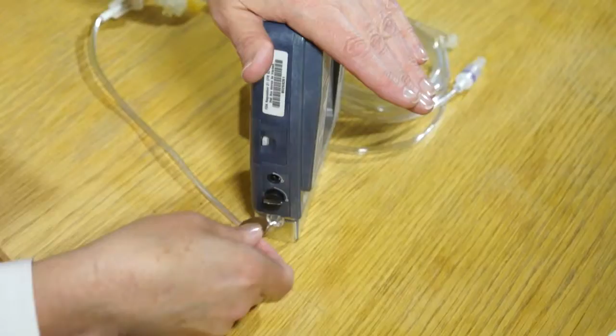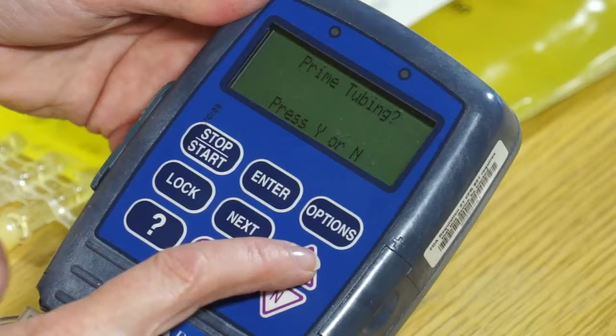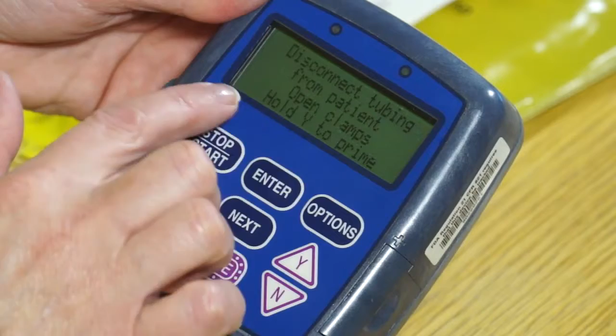Then press the cassette down, using one hand to support the pump upright and the other using a coin to turn the lock. The pump will then say prime tubing Y or N. You want to press Y for yes. Priming the tubing simply means you are filling it up with the fluid from the bag and removing the air at the same time. The pump will say disconnect tubing from patient. This is just an alert to make sure that you don't have it hooked up to the catheter yet.